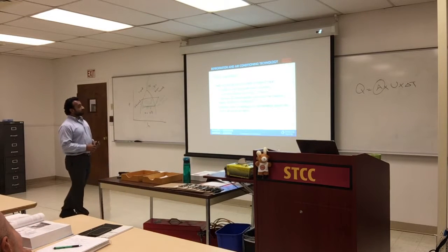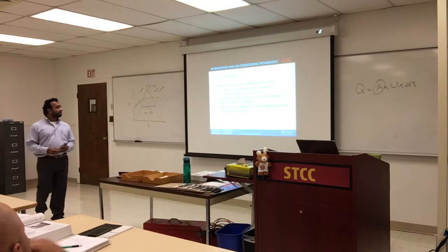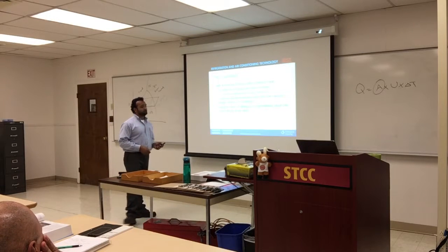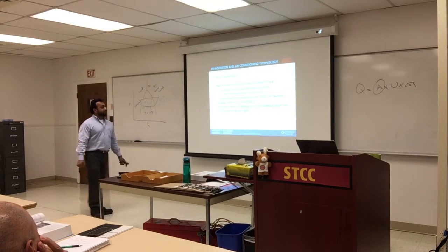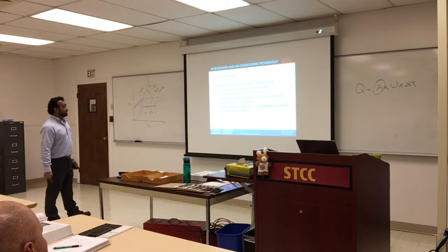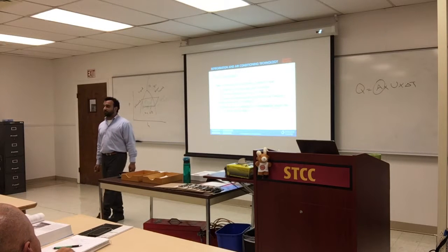Okay, so one by one, the evaporator is a heat exchange surface used to absorb heat. Located on the low pressure side of the system between the metering device and the compressor. Operates at a temperature lower than the medium being cooled or conditioned. And absorbs heat by boiling low temperature liquid into low temperature vapor.